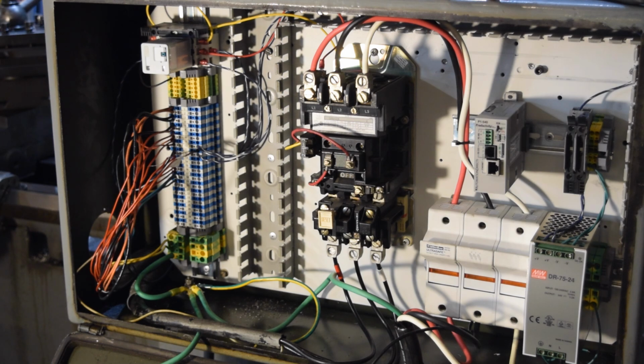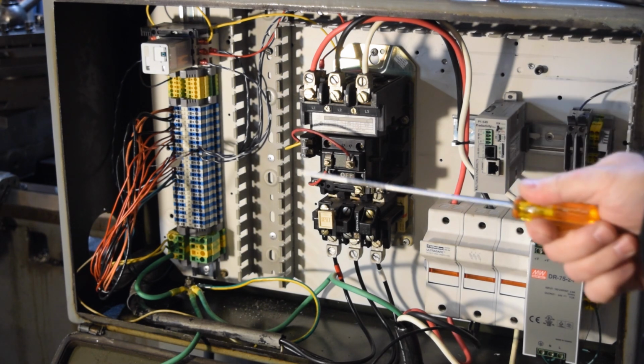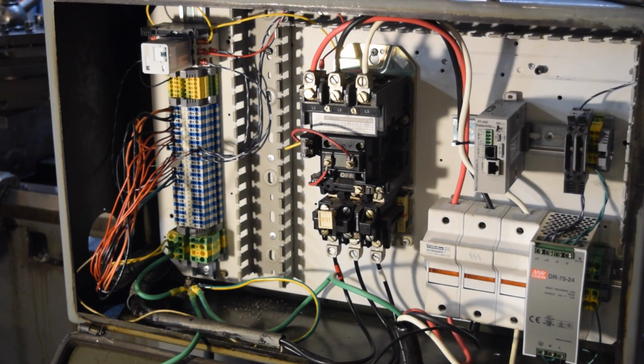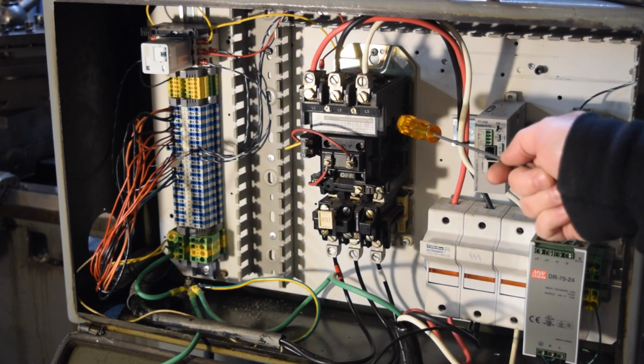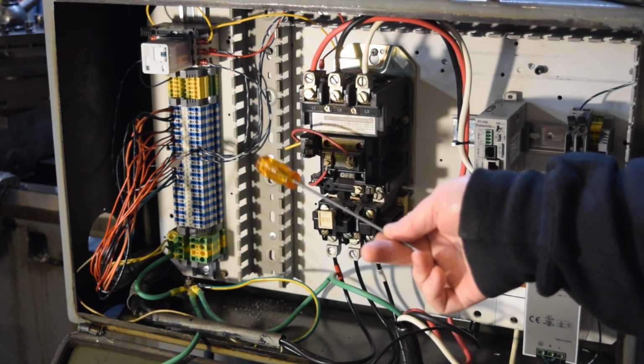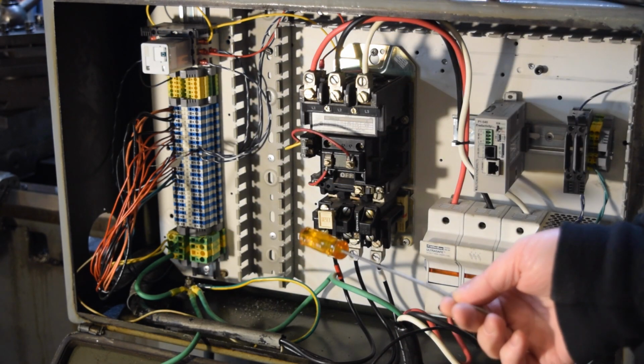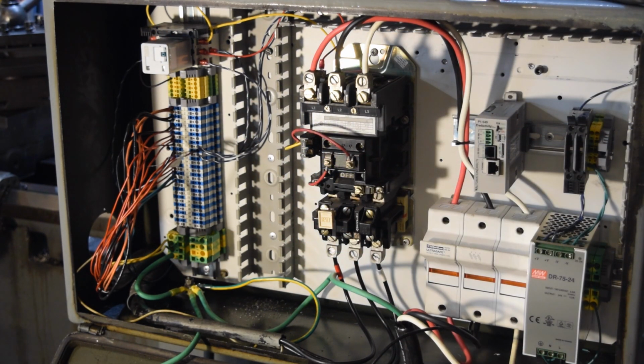Anyway, it was using straight 240 as the control voltage out to the switches, and I don't really like 240 volt control voltage. So what I did was I rewired. I took the wires that were originally controlling the contactor, wired them to this octal relay here, and then I used the octal relay to switch the high voltage to trigger the contactor in place of the switches directly. I like to keep the high voltage in the box if at all possible. So there you go. And it works fine.